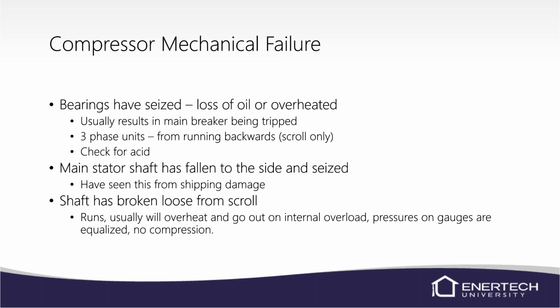Compressor mechanical failure, bearing seize, it could have loss of oil. We had somewhat of an issue back in the day with some of the water-to-waters running them at really high water temperatures and having some oil return problems. And we put some oil separators in and things like that. So obviously we've got to have oil in that compressor. It's a motor and it will overheat and burn up if you don't have oil in it.